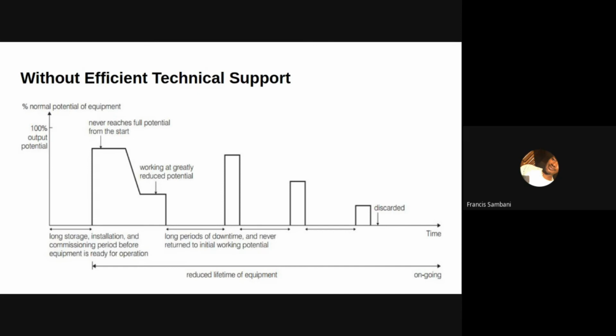An easy check for a compressor would be to connect a pressure gauge to the compressor outlet, and block the relief valve by removing it and fitting a fitting that has no output at all. You then switch on the compressor and read the maximum pressure that you're getting from that compressor. Then you can compare that to the maximum output pressure of that compressor, which you find in the manufacturer's performance chart. If the pressure reading you're getting from the compressor is low, that means the compressor needs to be serviced. So that's it on how you can monitor the performance of the compressor.